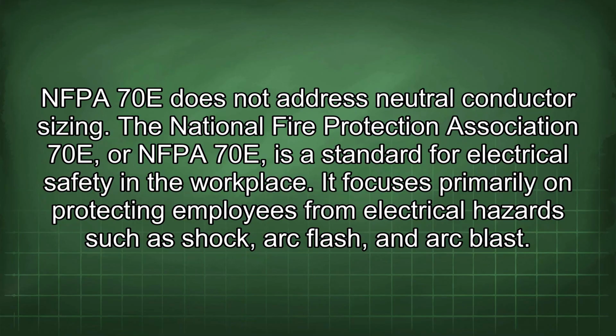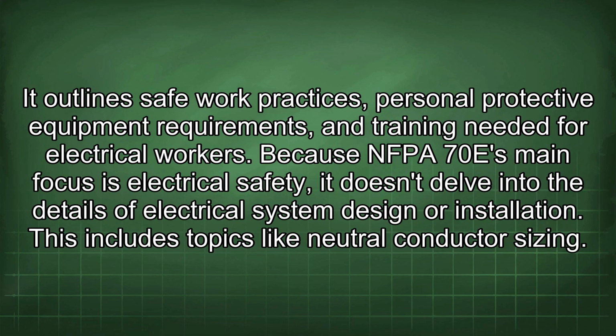NFPA 70E does not address neutral conductor sizing. The National Fire Protection Association 70E, or NFPA 70E, is a standard for electrical safety in the workplace. It focuses primarily on protecting employees from electrical hazards such as shock, arc flash, and arc blast. It outlines safe work practices, personal protective equipment requirements, and training needed for electrical workers.